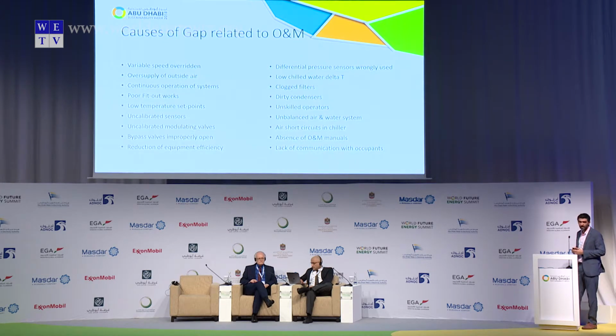Lower temperature set point. Many of us like lower temperatures, which is okay. But sometimes I get to see data centers or server rooms where the set point is 17 degrees. And this is seriously happening in many cases. And when I ask the IT person, why do you put the set point at 17? I don't get any document or any proper answer. In fact, most server rooms can live normally at 24 degrees, if not even higher. So this is a common thing I see in buildings over here.